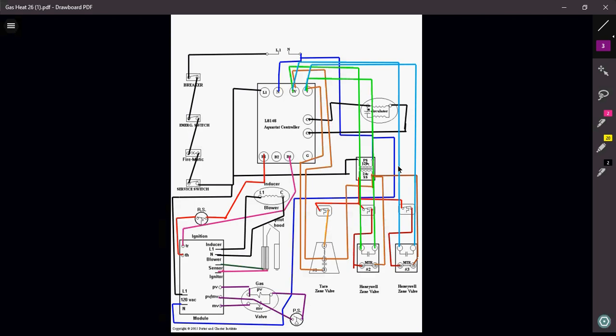Once that aquastat receives that signal that one of those thermostats has now called for heat, it is now going to send that signal down to your burners and your ignition module, your inducer motor. All that stuff is going to start to work. Your inducer motor is going to spin. And if everything is right with the flue pipe and your combustion chamber and all that, the pressure switch will close. Once that pressure switch closes, the gas valve and your pilot and all that stuff will ignite, which will then heat the boiler. And then at approximately about 160 degrees or so, the aquastat will now sense that temperature of the water and then energize your circulator.